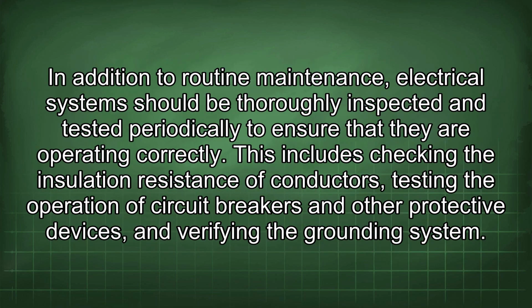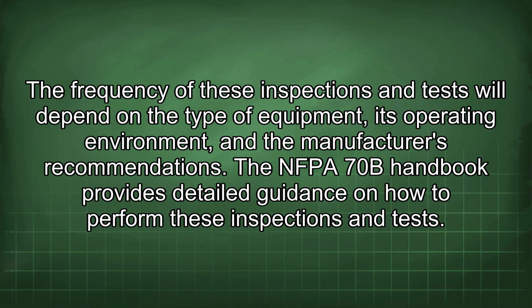In addition to routine maintenance, electrical systems should be thoroughly inspected and tested periodically to ensure that they are operating correctly. This includes checking the insulation resistance of conductors, testing the operation of circuit breakers and other protective devices, and verifying the grounding system. The frequency of these inspections and tests will depend on the type of equipment, its operating environment, and the manufacturer's recommendations. The NFPA 70B handbook provides detailed guidance on how to perform these inspections and tests.